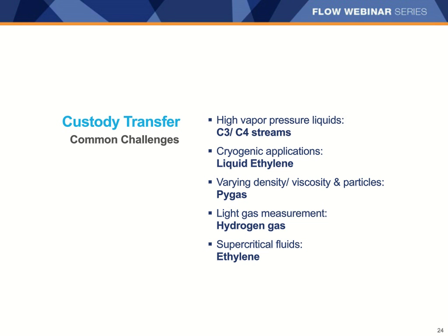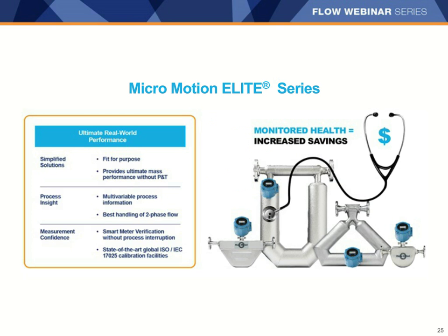Micromotion meters measure mass flow directly, which eliminates a lot of these challenges. However, not all Coriolis meters are equivalent on these difficult applications, especially when it comes to two-phase flow capabilities. Micromotion Elite meters offer direct mass metering — all these products are traded on a mass basis. They offer multivariable measurement with superior mass flow and density measurement capabilities under real-world conditions, so when your pressures and temperatures aren't the same as your lab environment. The volumetric output can be useful in ensuring tanks aren't overfilled even if the transaction is completed in mass. We provide maintenance-free operation even under heavy flashing and two-phase flow conditions. And smart meter verification enables you to check the meter integrity periodically and minimizes your proving requirements without interrupting the process at all.